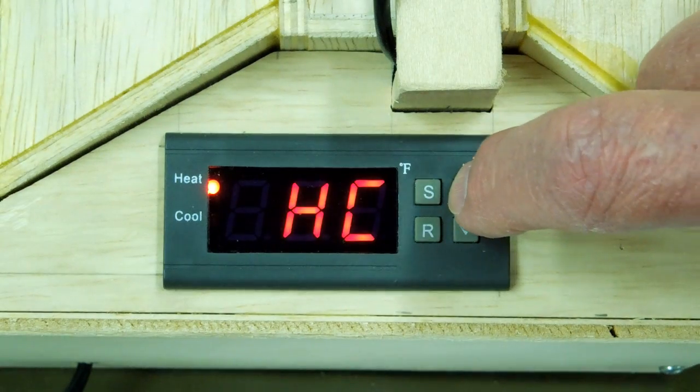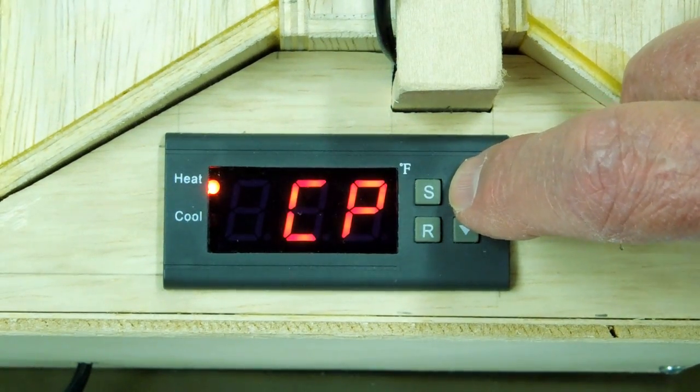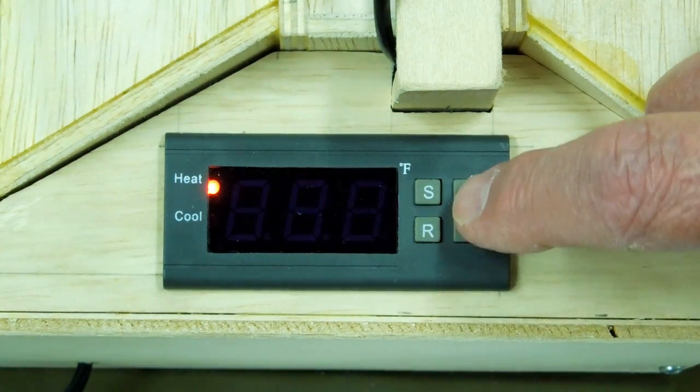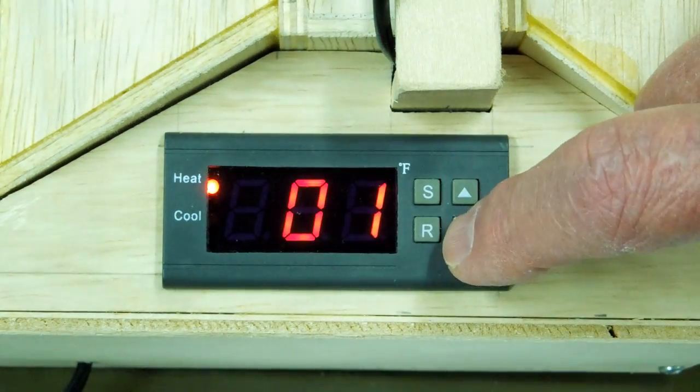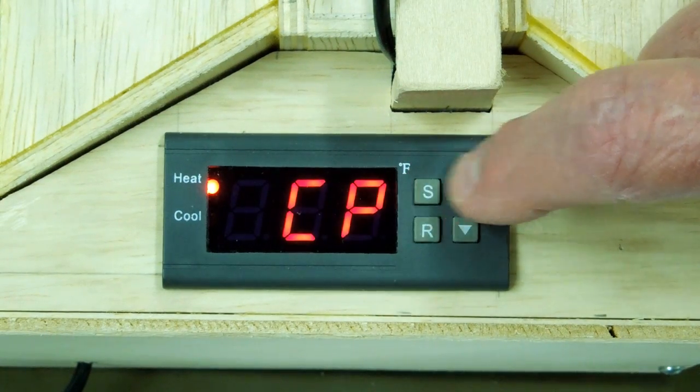Press that again. We come to CP which is temperature difference. I push S. I have it set at 1 degree. I can make that 2 degrees, and I can't go any lower than 1 on the Fahrenheit controller. Back to CP.